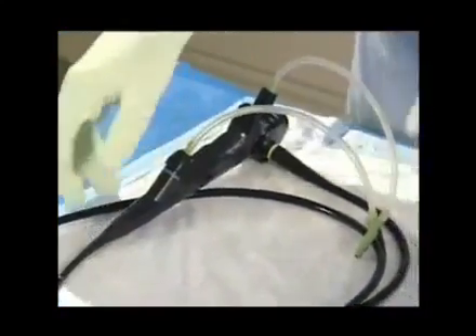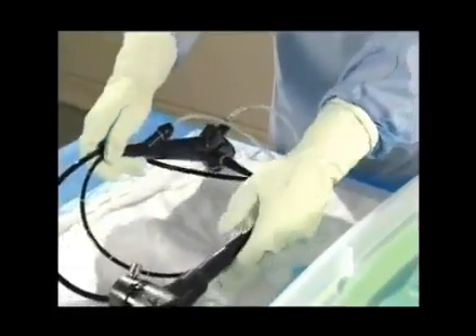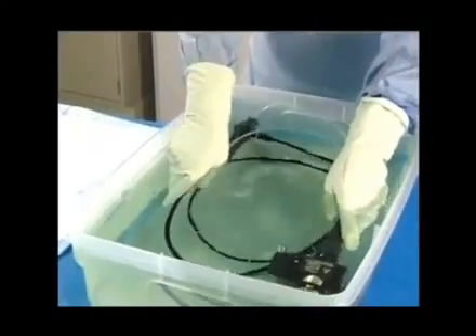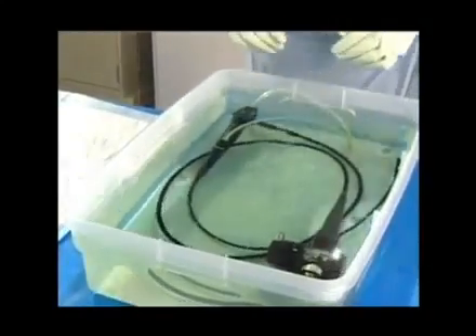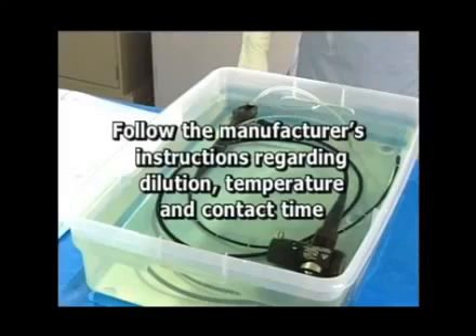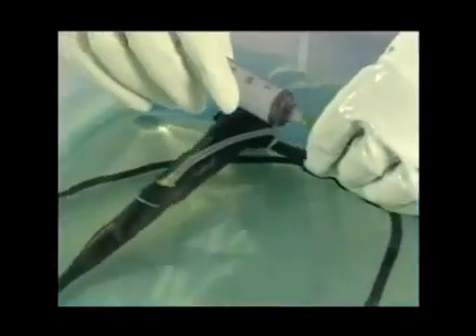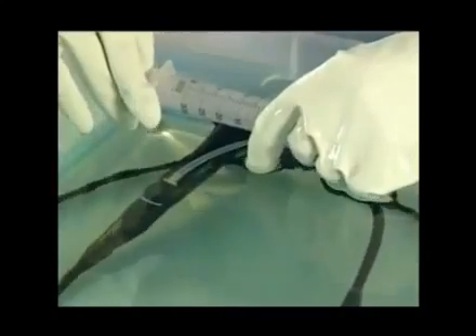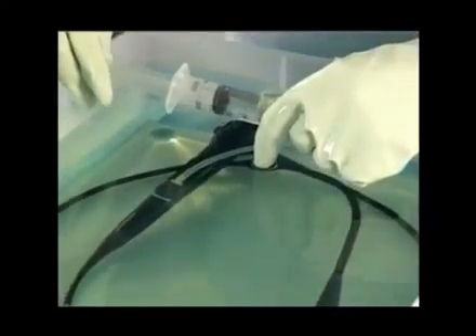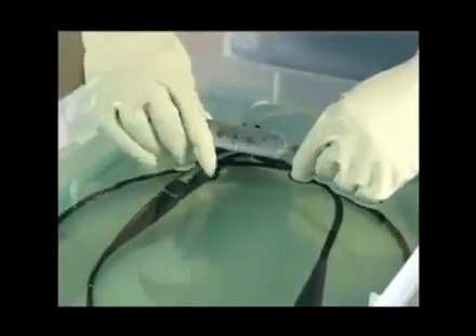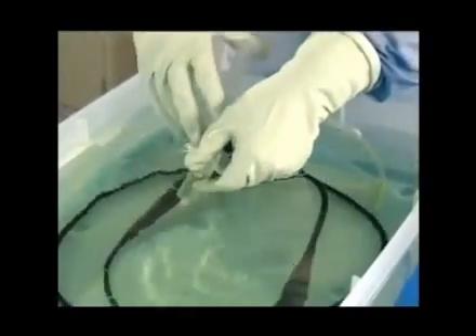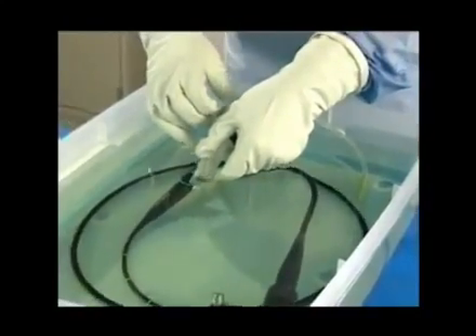Make sure that the suction cleaning adapter is attached to the bronchoscope. Immerse the bronchoscope and cleaning adapter in a compatible high-level disinfectant solution. The solution must be tested for efficacy and prepared according to the manufacturer's recommendations regarding dilution, temperature, and contact time. Attach a syringe to the cleaning adapter and withdraw the plunger to bring disinfectant into the channels of the bronchoscope. Check to make sure that both tubes of the suction cleaning adapter are filled with disinfectant solution.